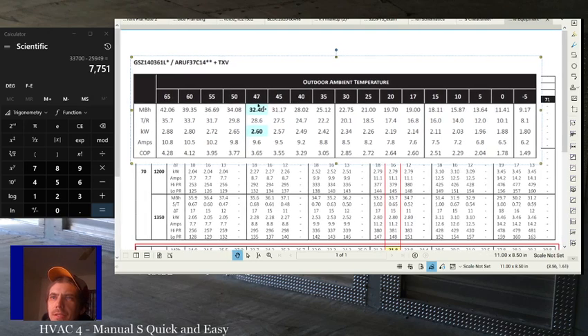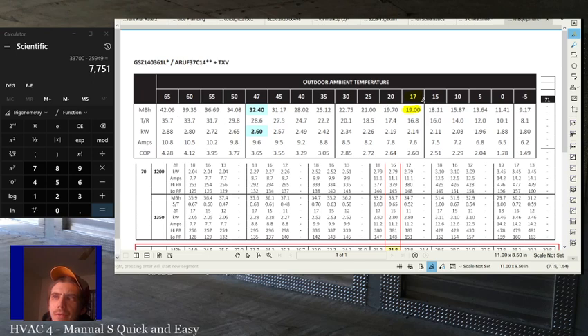So we can see this equipment puts out 32,000 BTUs at 47 degrees. Sometimes, especially if we're doing mini splits or something where we don't have electric heat, what we need to know is the heating output at our 17 degrees outside. So this 3-ton equipment at 17 degrees outside puts out 19,000 BTUs. If you want to size your electric heat really close, some jurisdictions will allow you to only size your electric heat to make up the difference between what's required and what the heat pump won't do. But that's not really recommended. In general, you size your electric heat to 100% of load.